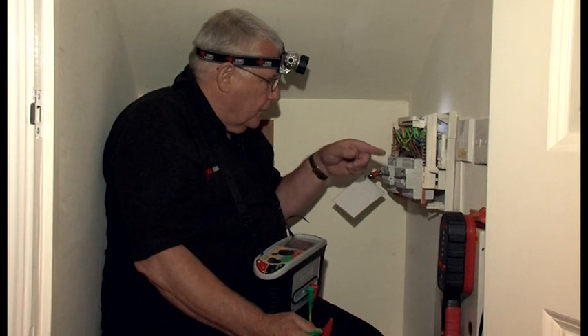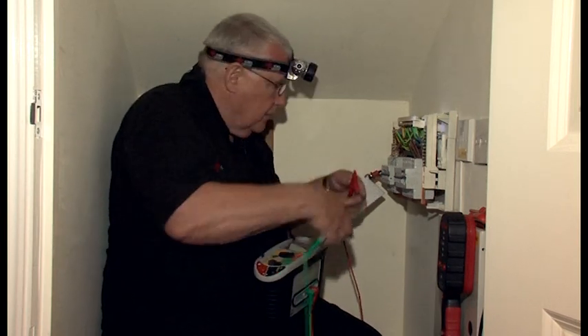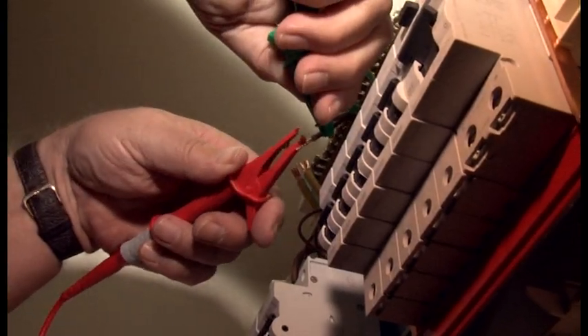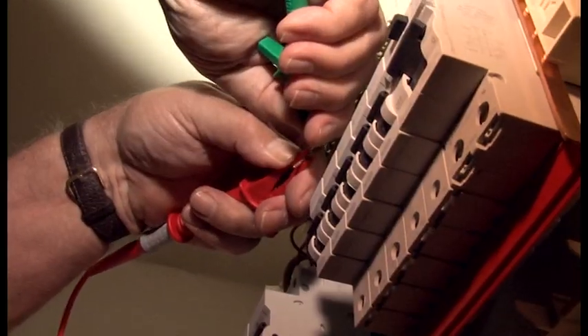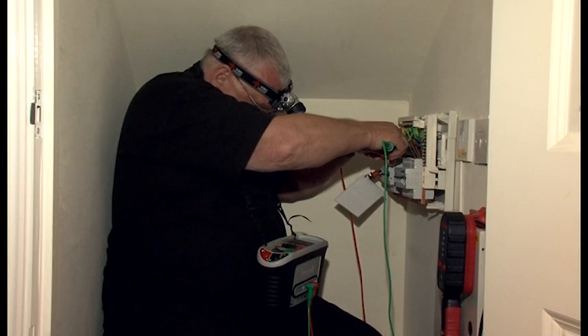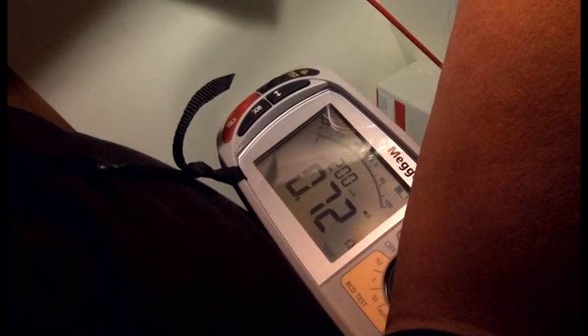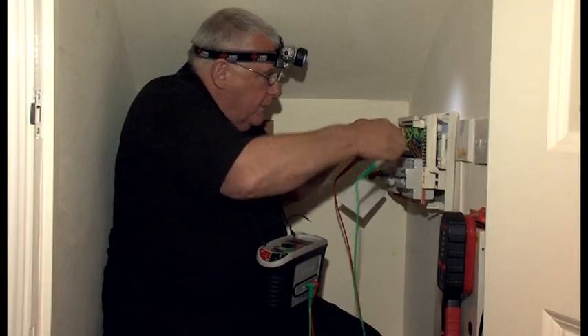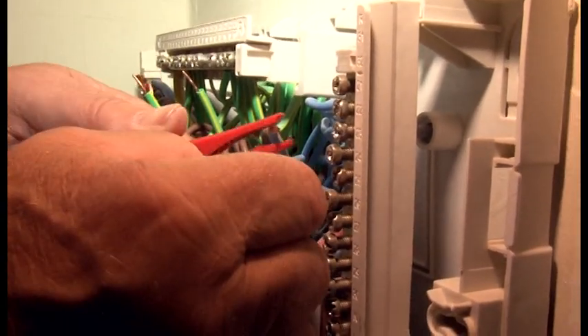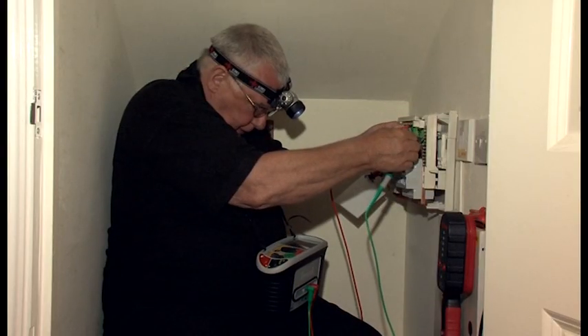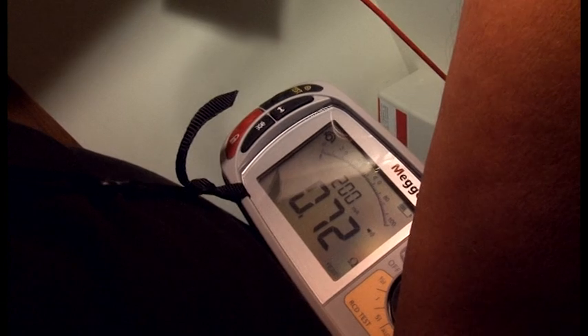I'm going to carry out my end-to-end test. I have nulled out the instrument. The first thing I'm going to do is on line to line. Now I have a reading, so that proves it is a ring, and the reading I've got is 0.72 of an ohm. Now I'm going to do the same with the neutral. Once again I've got a reading, so it's a ring, and I would expect roughly the same, and believe it or not, it's exactly the same, 0.72 of an ohm. Well, sometimes there are small variations, which can be caused by bends in the cable, causing one conductor to be slightly longer than the other. And of course, the tightness of each and every termination will also have an effect on the overall resistance reading.